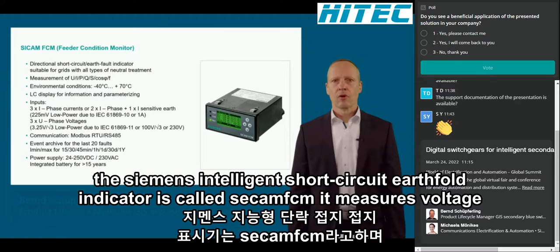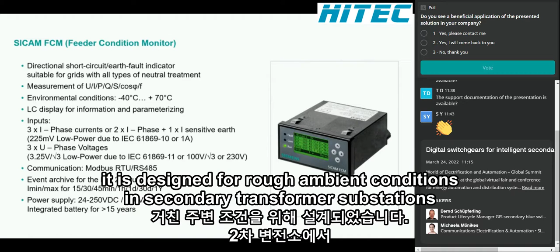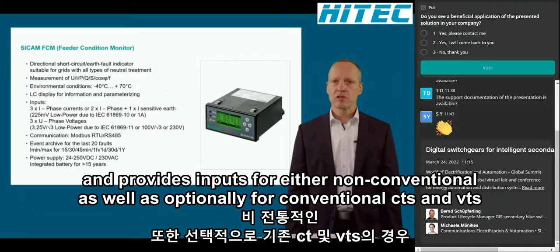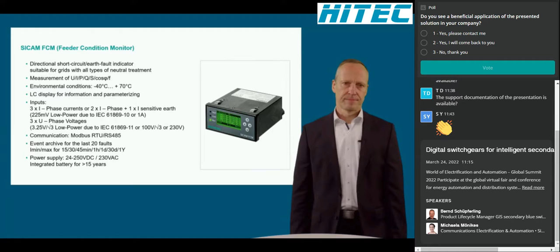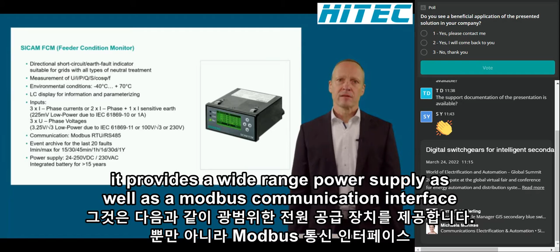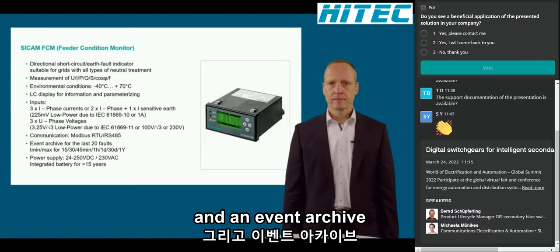The Siemens Intelligent Short Circuit Earth Fault Indicator is called SICAM FCM. It measures voltage, current, and can calculate all kinds of powers, cosine phi, and the frequency. It is designed for rough ambient conditions in secondary transformer substations and provides inputs for non-conventional as well as, optionally, conventional CTs and VTs. It provides a wide range power supply as well as a Modbus communication interface and an event archive.